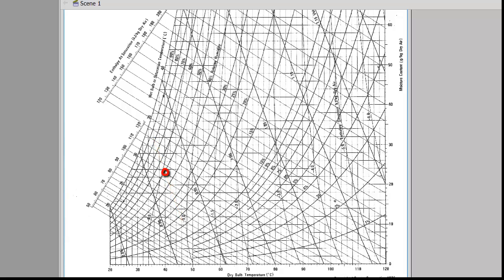For the dew point, note that the humidity ratio remains the same but the dry bulb temperature decreases. So we follow a horizontal line from the point toward the left-hand side to where it meets the 100 percent relative humidity curve, or the saturation curve, and read the temperature there. From there we find the dew point to be 27.5 degrees C.